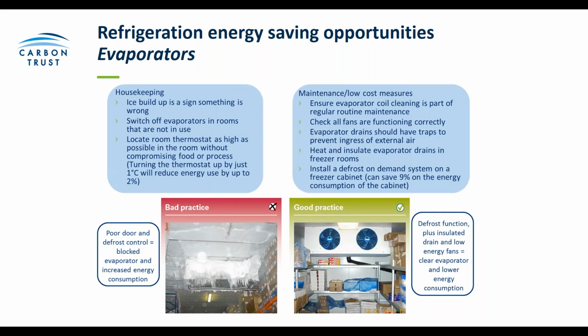So evaporators. So this is where heat's collected. So again, make it really easy for that heat to be collected. Keep an eye on them. Make sure that if you see any permanent buildup of ice, that you investigate that. That's a good indication that something's gone wrong. Where there are evaporators in rooms such as production areas, you can switch these off when the rooms aren't being used. Evaporator controller is usually the room thermostat, so make sure that this is set as high as possible without compromising obviously the product you're trying to keep chilled.